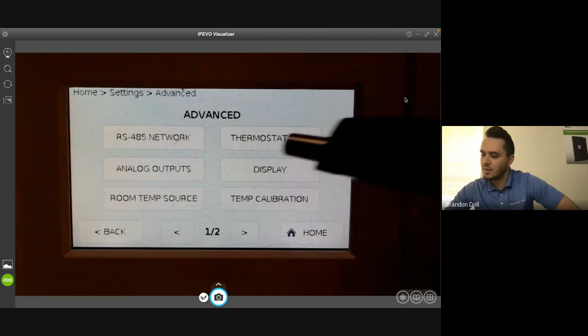Right from this page, you just hit your analog output. You can set it for your heat, your cool, or your economizer. I'm going to put this on the economizer. For the action, you can do direct or reversing. You can do 4 to 20 or 0 to 20 milliamps. I'm going to hit direct, save. And now analog output 1 is set up for the economizer in direct action and is going 4 to 20 milliamp. Now, if you wanted to do that in voltage, every single one of our UbiquiSTATs comes with a 500 ohm resistor. You just connect that to ground and convert it over to voltage.